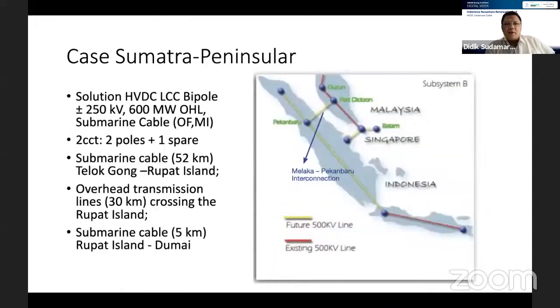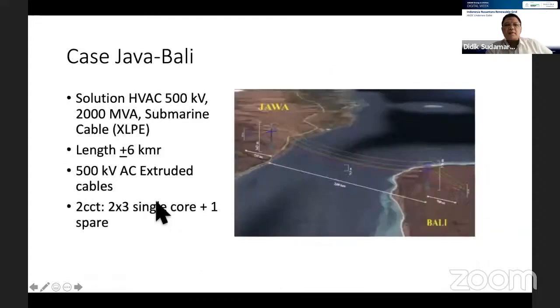This is the Sumatra-Peninsular Malaysia case, using 250 kV, about 600 megawatts total, meaning 300 megawatts per pole, using 2 poles, 1 spare, 2 circuits. This is about 52 kilometers of submarine cable, plus 5 kilometers, plus 30 kilometers of overhead line.